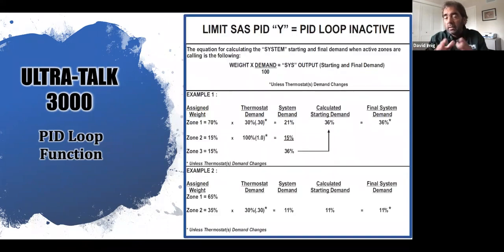Now, if I look at that loop and let's just say I selected Y, I do not want that PID loop involved. I want to be very specific on how much demand, what stage I'm going to give those zones. I don't want it to have the ability to go into a higher stage than what I feel is necessary for smaller zones and or to satisfy my call for a minimal amount of zones calling. I decided to take the loop out of it. I would be very careful doing that. I would always let the loop be a part of the operation. I would almost always select N unless you fully understand what's going to happen if you select Y.